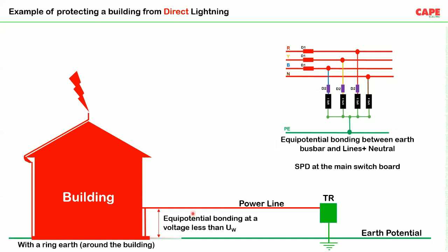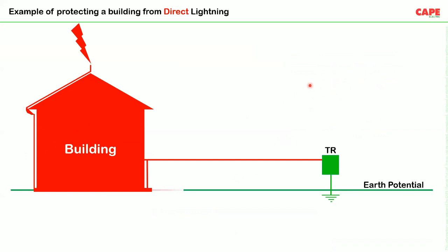Now, lightning is always a common mode phenomenon. For a common mode phenomenon, this kind of connection is much more efficient. The 4 plus 0 connection is much more efficient than a 3 plus 1 connection. But then, it depends upon your network, whether you are using TT or TN, where the earth fault protection is implemented.